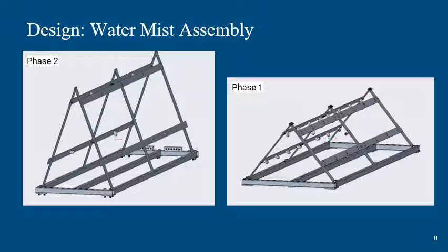Compared to Phase 1, the team noted that the stand geometry of the initial setup did not match the standard V of the Carrier chillers. The team altered the design so that the stand was taller, as well as having a shorter base, which assisted the mist coverage of each nozzle as they spray in a cone pattern.